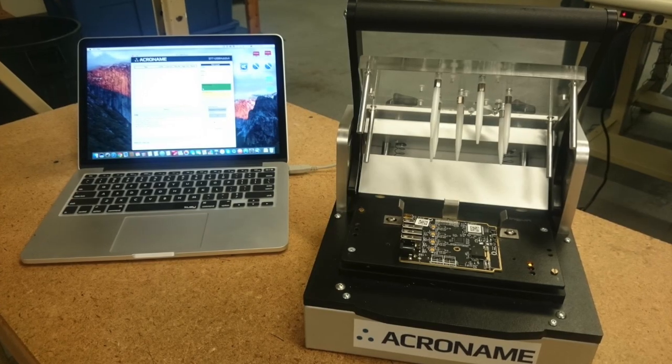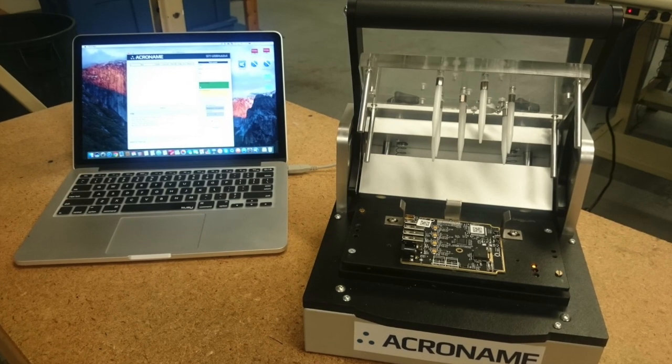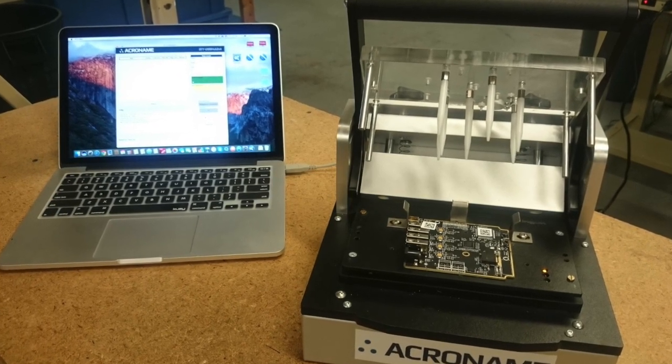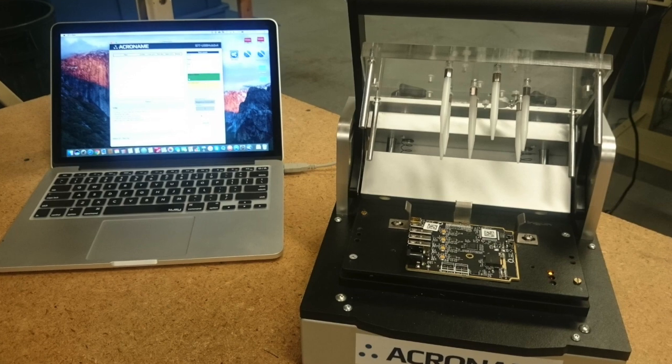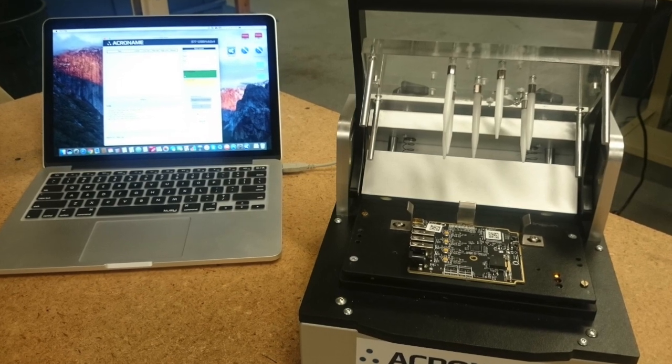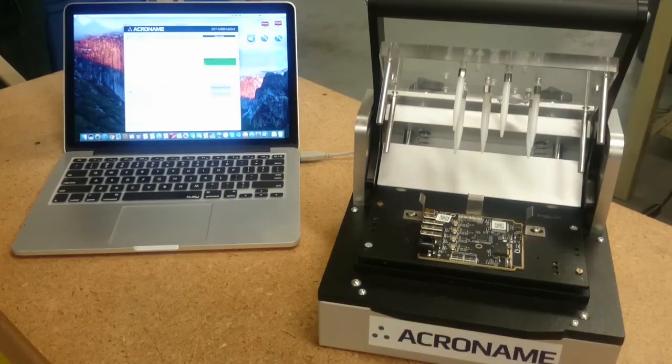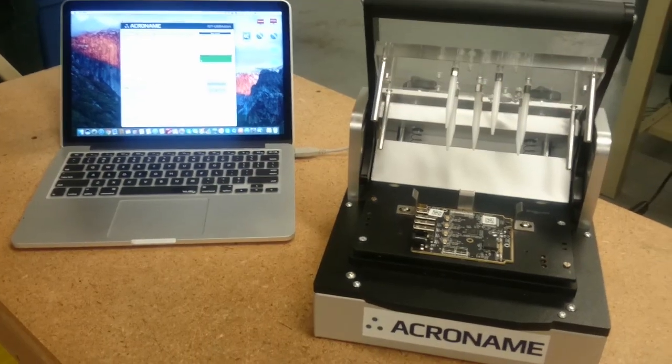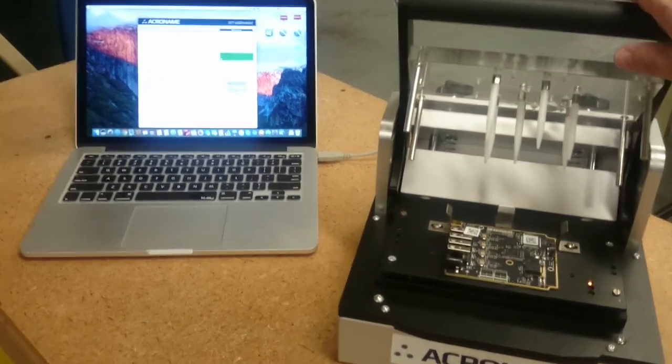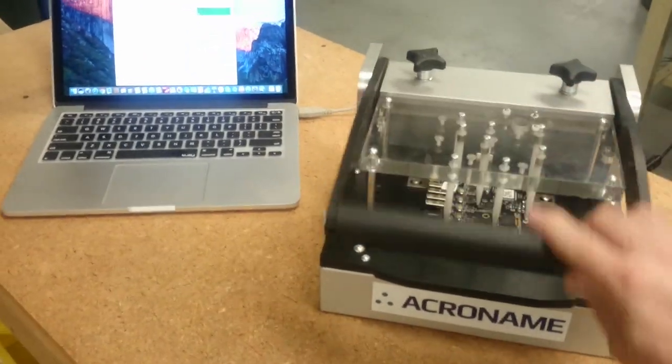A host machine running a Python script will execute tests through the MTM modules and then collect the resulting test data. Just closing the lid will start the Python test script running on our host machine.